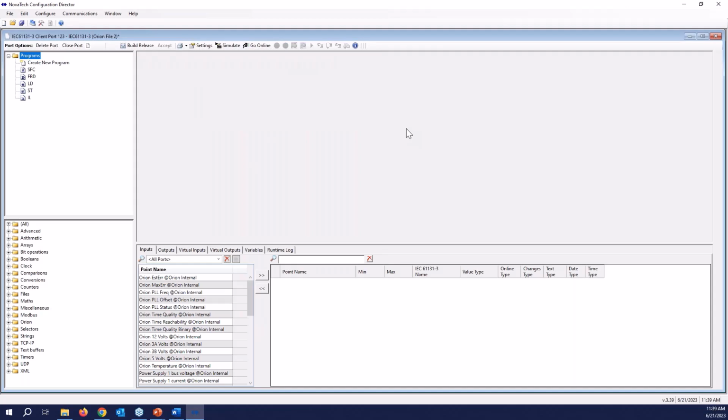So when do you use UDFBs? If you're using like a recloser scheme or auto changeover scheme, it's the same from feeder to feeder, and you don't want to do the same thing over and over. That's when you create the UDFB once, and you call it on your main program. So the example that I'm going to do is a simple one where you're monitoring count failed points from substation A with 5 or 6 count failed points. If one of them is on for 5 seconds, go ahead and send a control out or set a virtual 61131 point to high, and we can map that point to SCADA master.